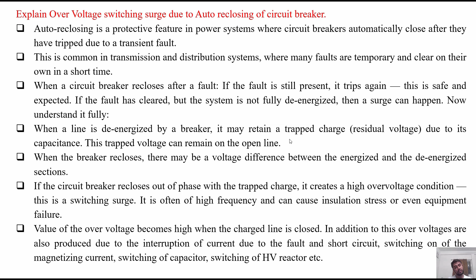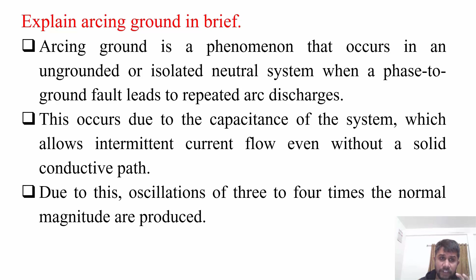So arcing ground is a phenomenon that occurs in an ungrounded or isolated neutral system when a phase to ground fault leads to repeated arc discharges. This occurs due to the capacitance of the systems, which allows intermittent current flow even without a solid or conductive path. Due to this, oscillations of 3 to 4 times the normal magnitude are produced. So these are some points or brief information regarding arcing ground. State the causes and effects of arcing grounds.